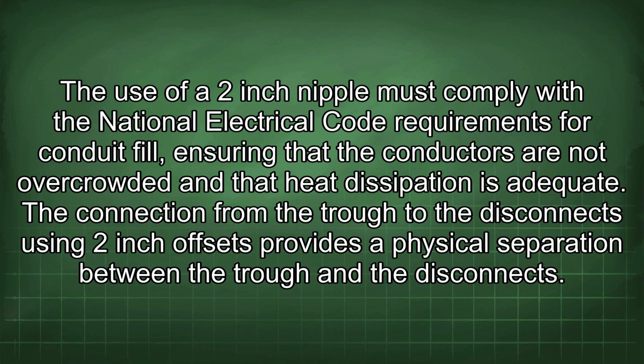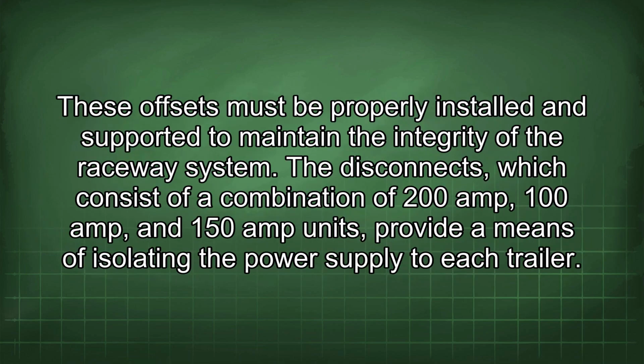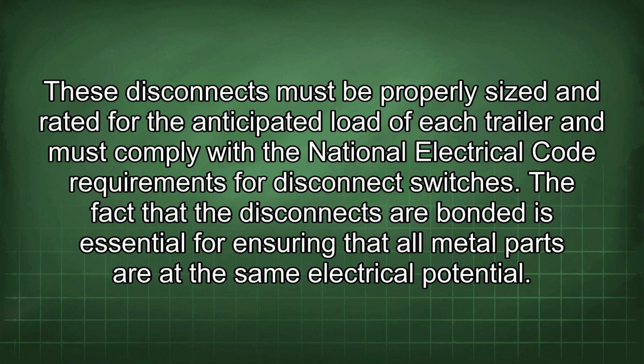The connection from the trough to the disconnects using 2-inch offsets provides a physical separation between the trough and the disconnects. These offsets must be properly installed and supported to maintain the integrity of the raceway system. The disconnects, which consist of a combination of 200 amp, 100 amp, and 150 amp units, provide a means of isolating the power supply to each trailer. These disconnects must be properly sized and rated for the anticipated load of each trailer and must comply with the National Electrical Code requirements for disconnect switches.